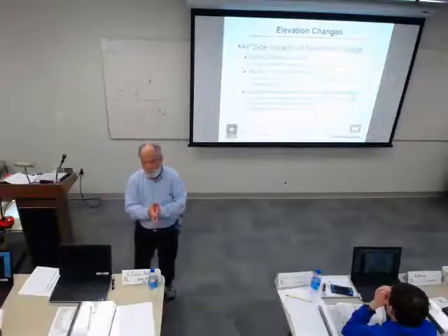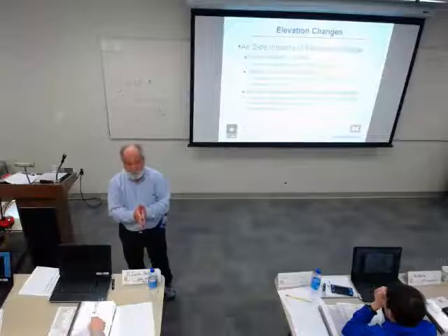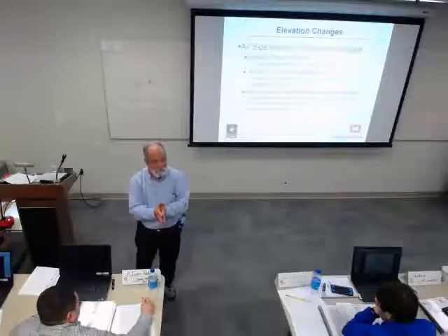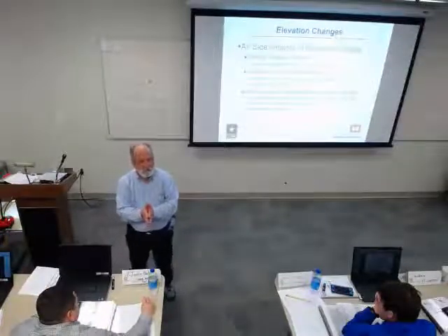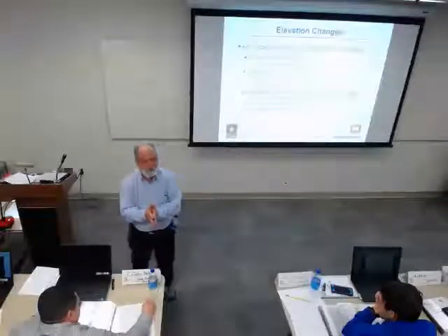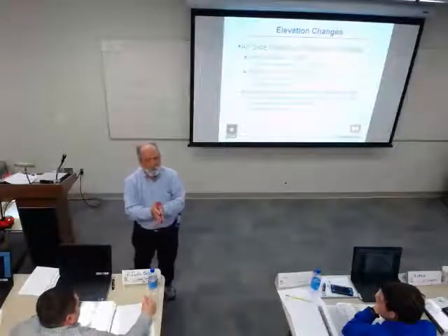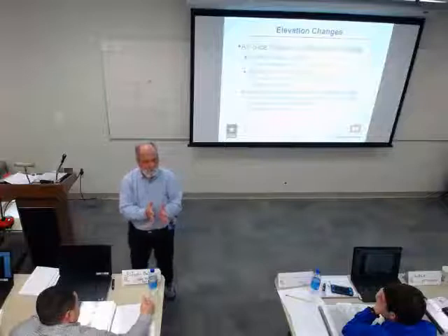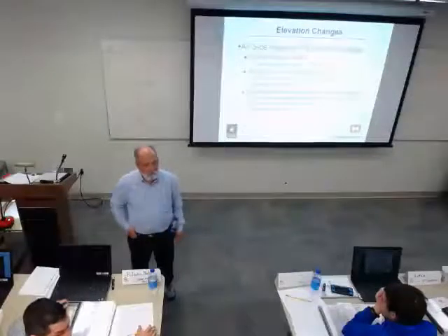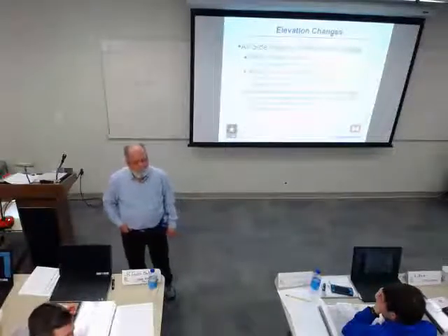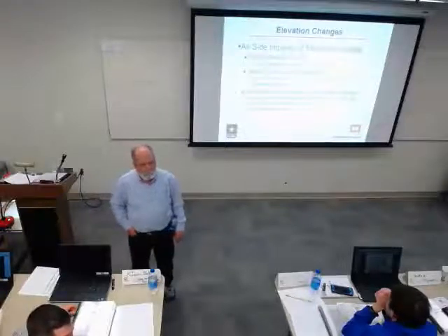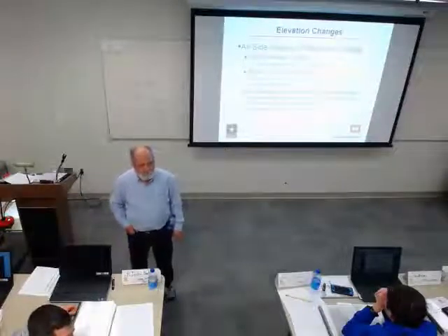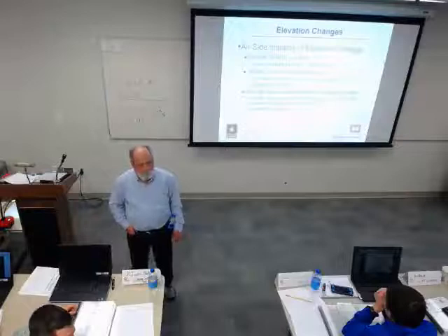My experience is that we're usually plus or minus something in the neighborhood of 8 to 12%. What's yours, Matt? When you compare water side balances, the heat transfer on the water side and air side, what do you usually see for matches within plus or minus? I've had that be, I mean, that's a tough one. Sometimes it lines right up, sometimes it doesn't.